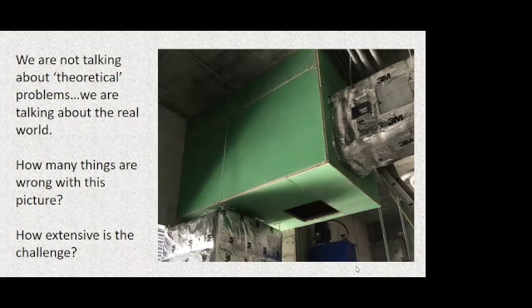The plenum box is the width of the fan enclosure. I use that term loosely. We'll talk about why. The plenum box is over 4 feet wide and well over 6 feet deep. It's approaching 8 feet deep. So once you know the constraints on drywall, once you know the constraints on the insulation class of products, you realize that that plenum box is well larger than the kind that allow a strap support.